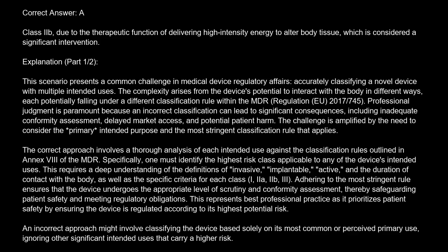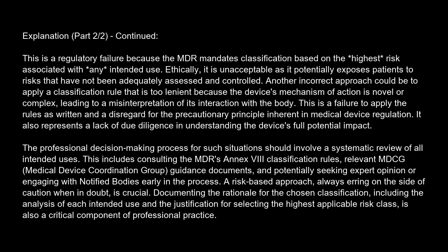This represents best professional practice as it prioritizes patient safety by ensuring the device is regulated according to its highest potential risk. An incorrect approach might involve classifying the device based solely on its most common or perceived primary use, ignoring other significant intended uses that carry a higher risk. This is a regulatory failure because the MDR mandates classification based on the highest risk associated with any intended use. Ethically, it is unacceptable as it potentially exposes patients to risks that have not been adequately assessed and controlled.